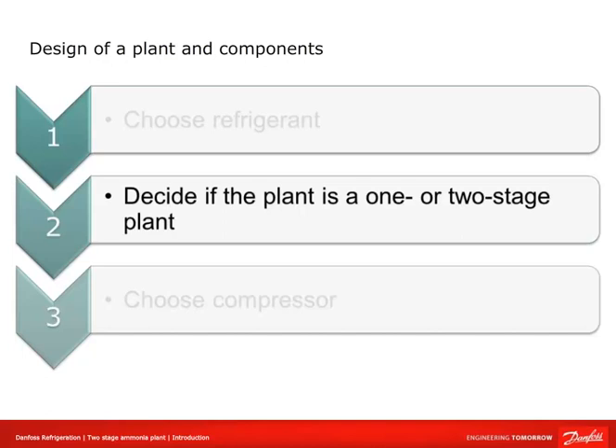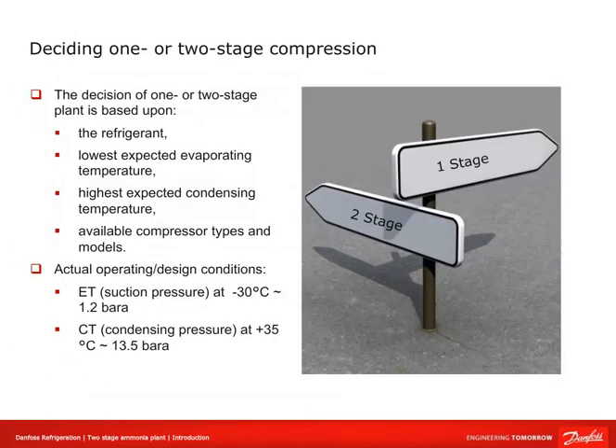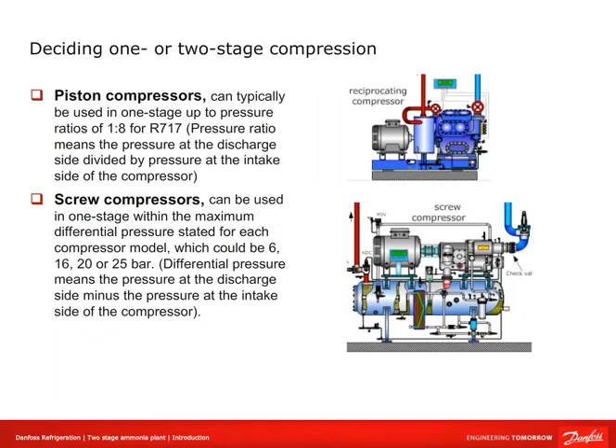We need to decide the number of cooling stages — one or two — which depends on the refrigerant chosen, the lowest evaporating temperature, the highest condensing temperature, and the available compressor types and models. The design conditions are a suction temperature of -30°C and a condensing temperature of +35°C. Piston compressors can typically be used in one stage up to pressure ratios of 1:8 for ammonia. Screw compressors can be used in one stage within a maximum differential pressure — which could be 6, 16, 20, or 25 bar — where differential pressure is the discharge pressure minus the intake pressure.